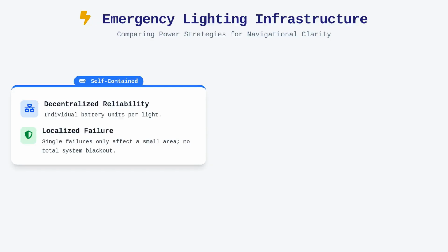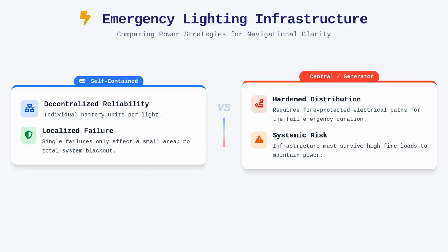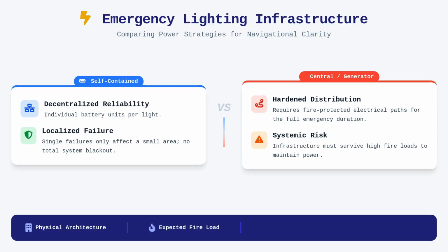When considering the infrastructure supporting these lights, keep in mind the difference between self-contained battery units and central battery or generator-fed systems. Self-contained units offer decentralized reliability, meaning a single component failure only affects a localized area, whereas a central system requires a hardened electrical distribution path that must be protected from fire damage for the duration of the emergency. If you are designing for a high occupancy hazard, the selection of the power source is often driven by the physical architecture of the building and the expected fire load. Regardless of the chosen technology, the primary goal remains absolute navigational clarity during a catastrophic power failure, which requires meticulous attention to both the hardware specifications and the environmental context into which they are installed.